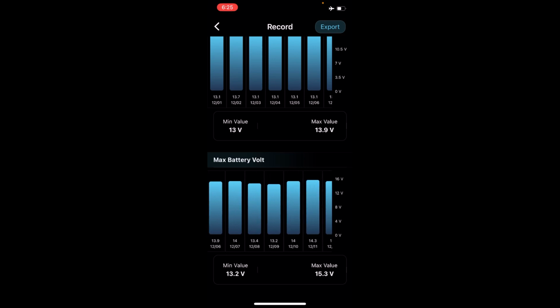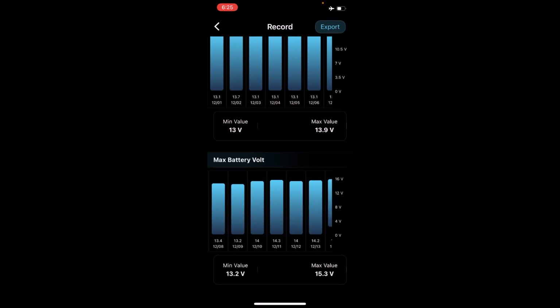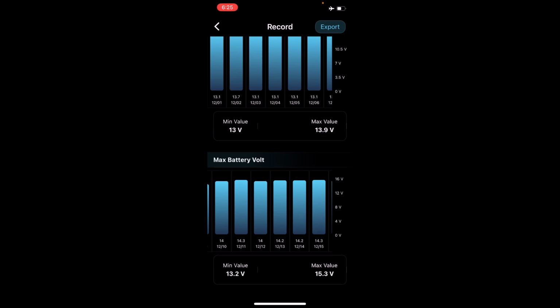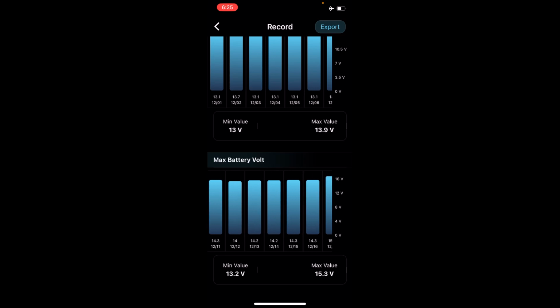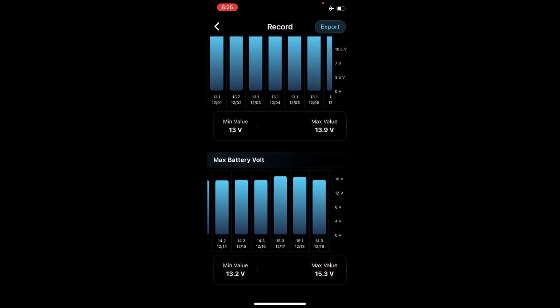There were a few days of no sun where it didn't charge back up, and then it went up to 14. So I turned it up a little bit, and it went up to 14.3, then only went up to 14 because there was a lack of sun. Then we see a couple days of 14.2, and then I think I turned it up to 14.3, but you'll see on the 17th it went to 15.3.